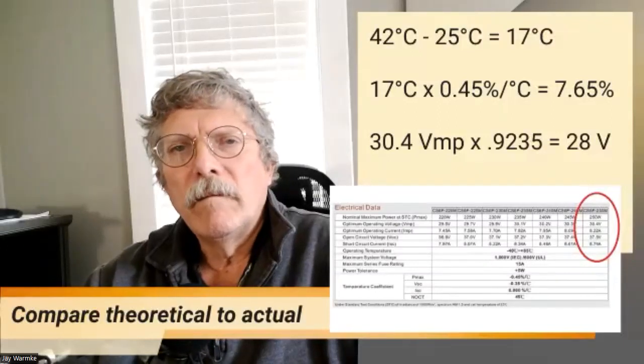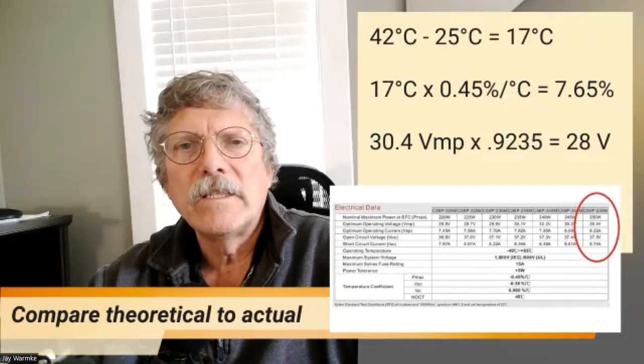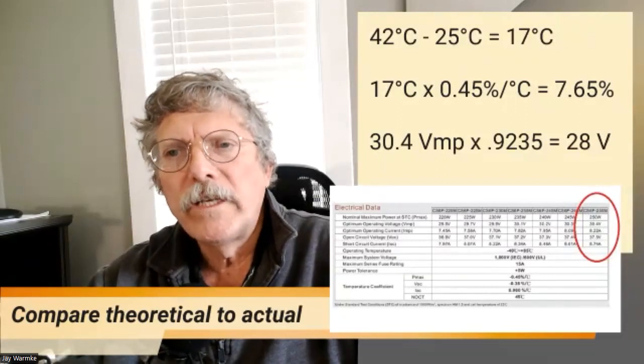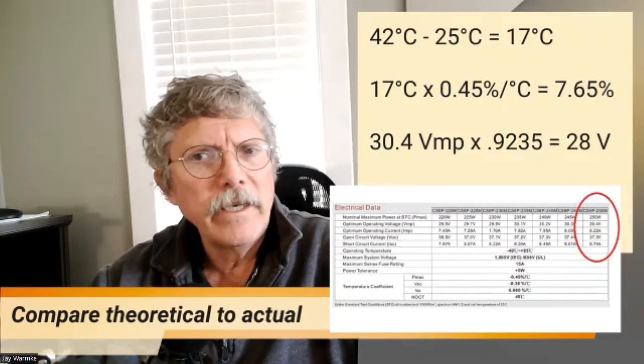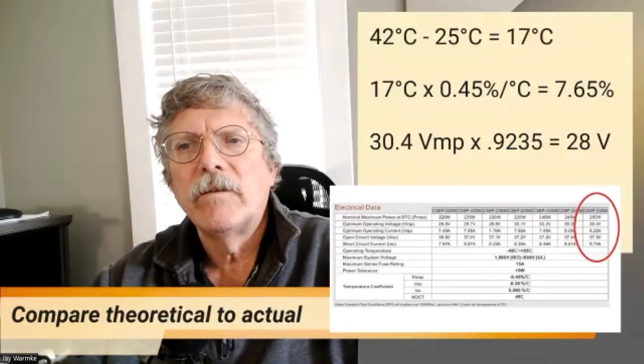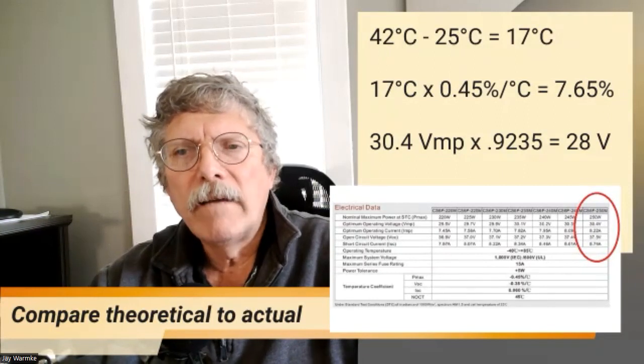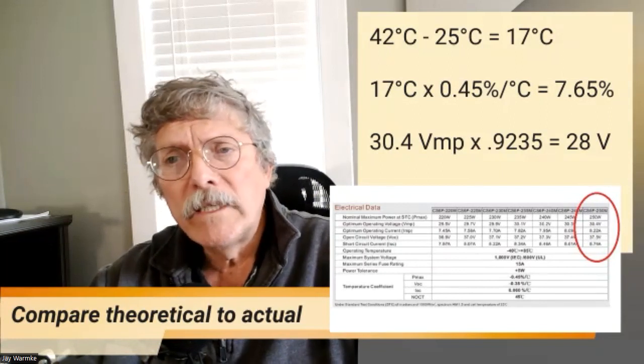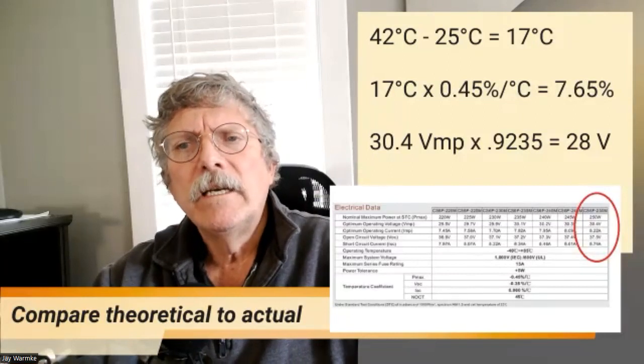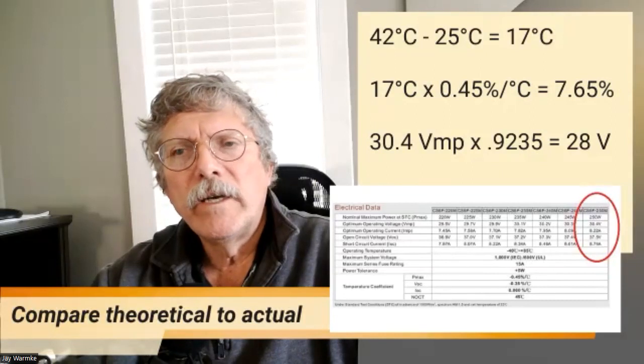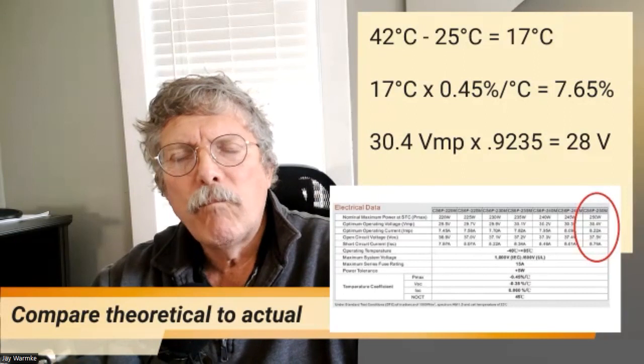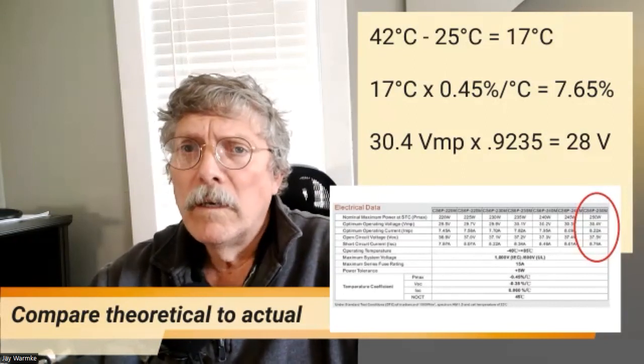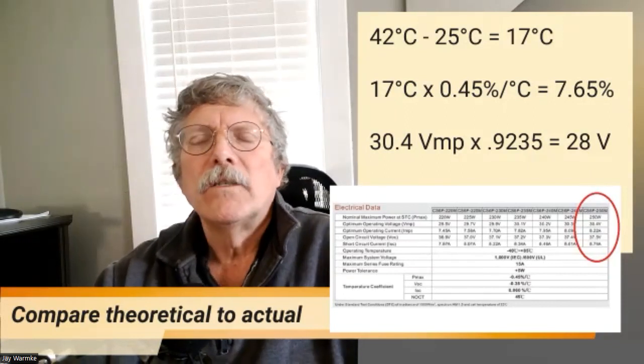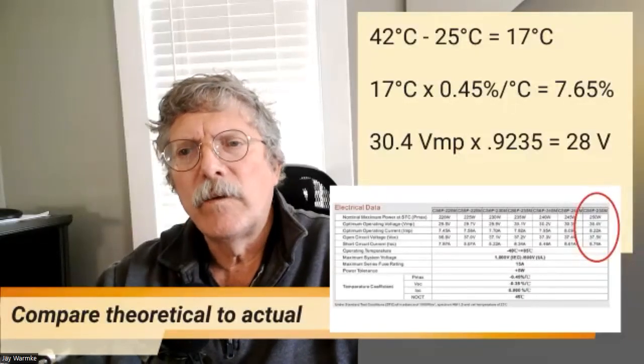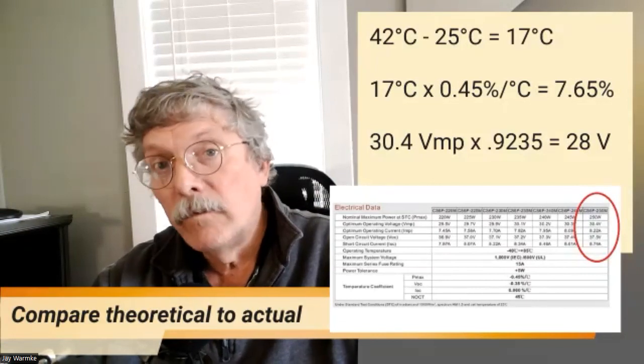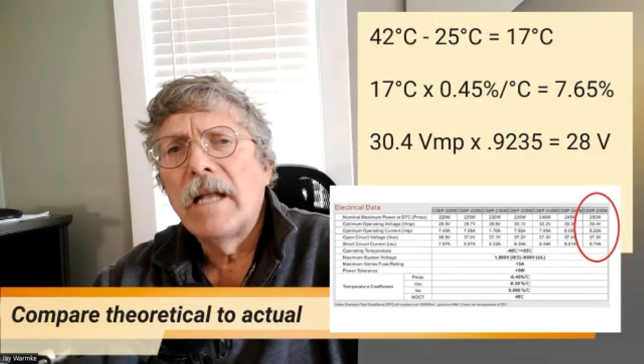All right, so armed with these numbers, from our reading in this example, we found that the cell temperature is 42 degrees Celsius. Well, we know standard test conditions are 25 degrees. So there is a delta, a difference, of 17 degrees Celsius. So 17 degrees Celsius times the temperature coefficient at Pmax, which is how much it is going to vary per degree Celsius. We take 17 times 0.45, and we find that this panel is going to differ from standard test conditions by 7.65%. Well, the temperature is warmer, so the panel is going to produce less power. So instead of producing at standard test conditions, we now know it's only going to produce 92.35% to be exact, of what the panel is rated for.